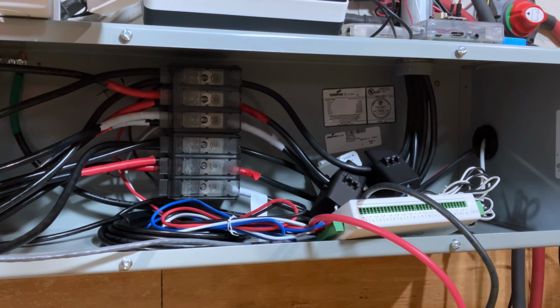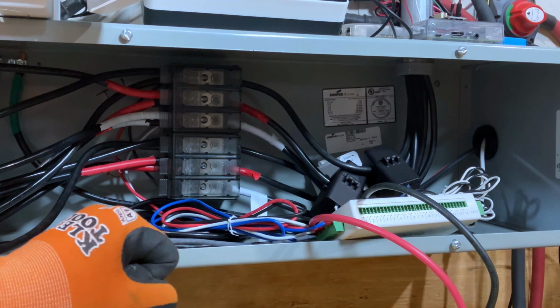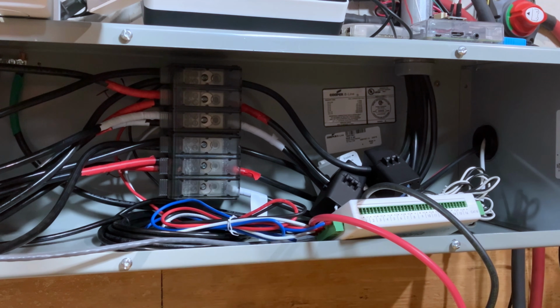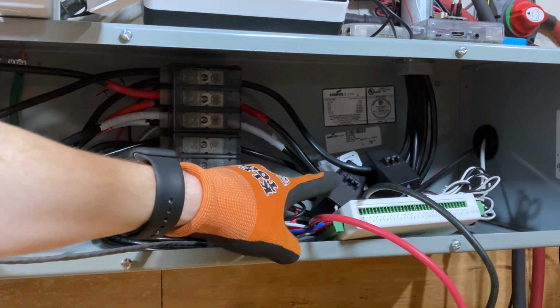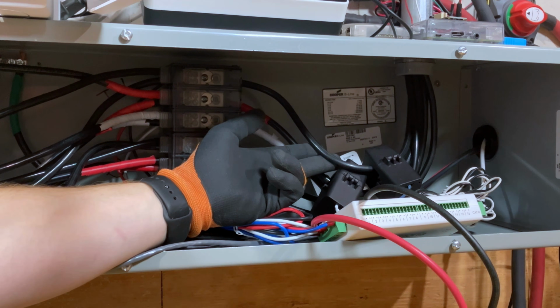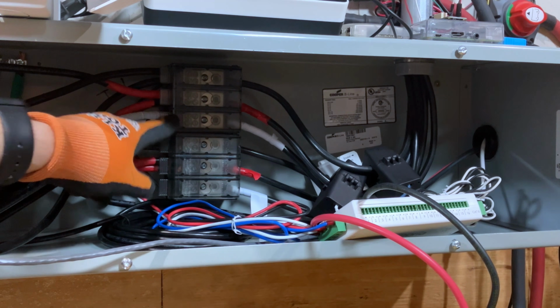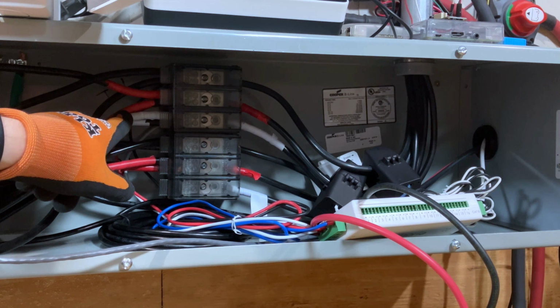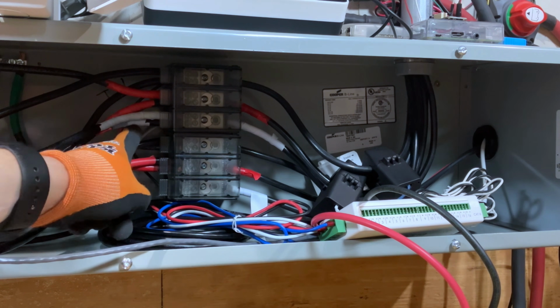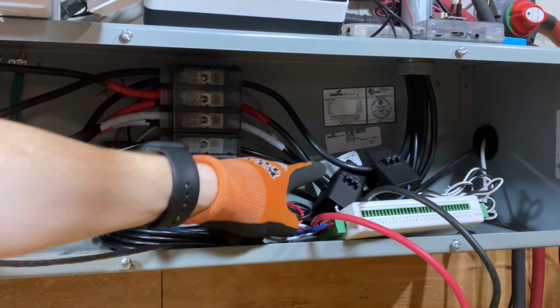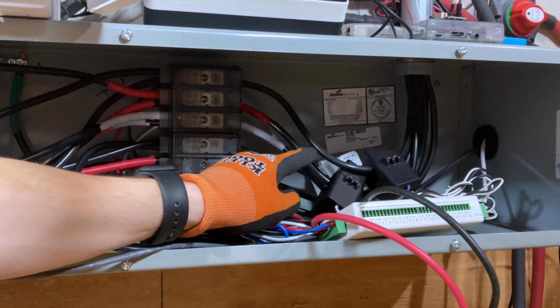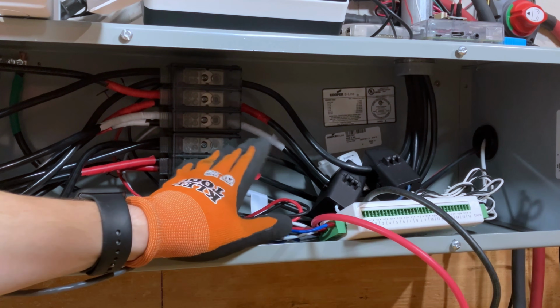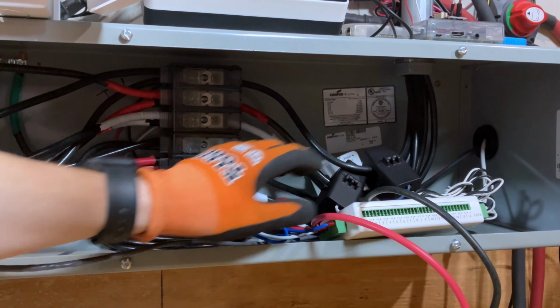If you're in self-consumption mode and you're selling back to the grid or backfeeding your main panel, then you want your CTs in your grid panel on your grid feed, just like you normally would for a self-consumption mode. If you're doing self-consumption with 0 export and you're not backfeeding the panel, you want to make sure that you put your CTs on the combined feed from your grid panel before you split that going to each individual inverter. Does that make sense? If you put the CTs on this side, it's only going to be reading power flow for one inverter, not both. You need to read the power flow for both inverters so that it can calculate everything properly and make sure that it's not backfeeding any power at all up to your grid panel.